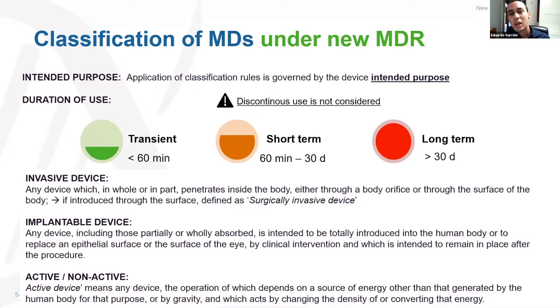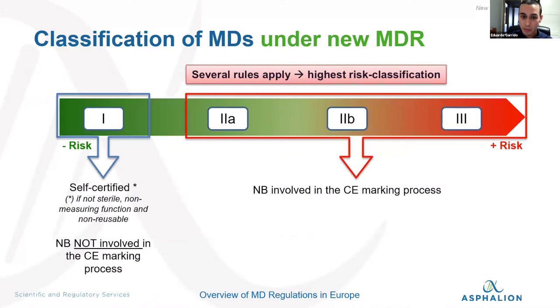Once you take into account all these points, you've got to identify which rules of the regulation apply to your device. Once you identify these rules, you will have pretty much laid out the class of your device. Your device can range from class one to class three, with one being the lowest risk and three the highest risk.